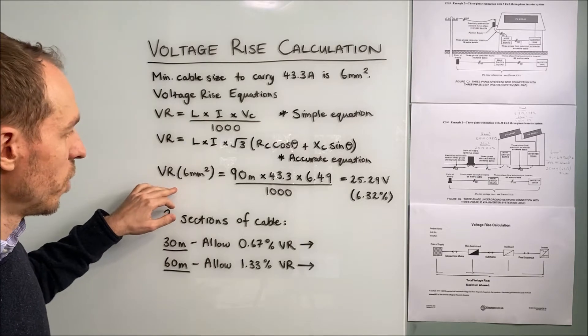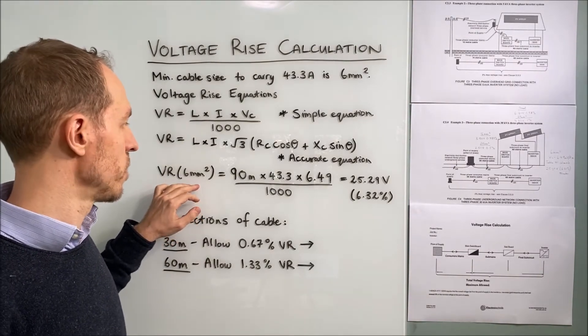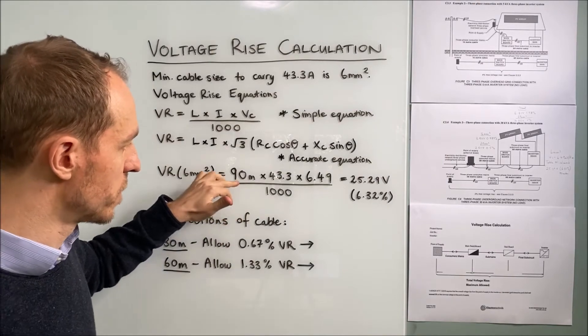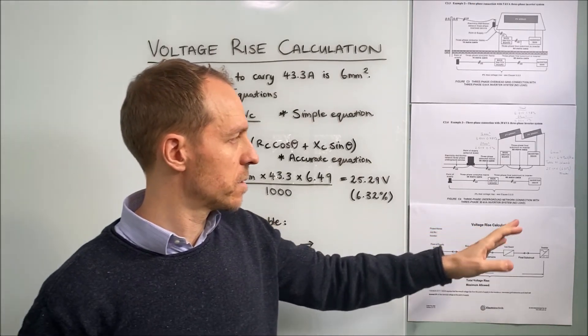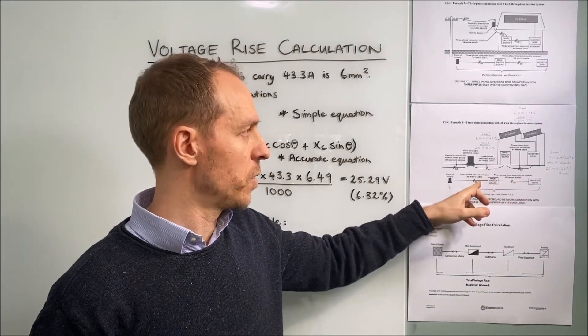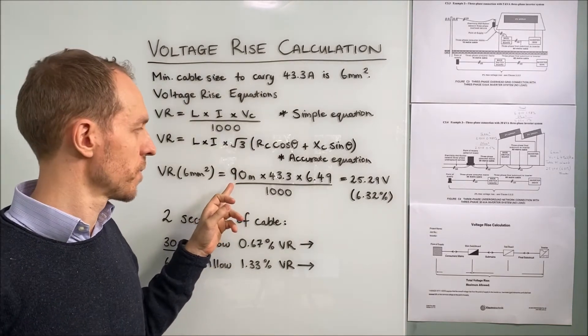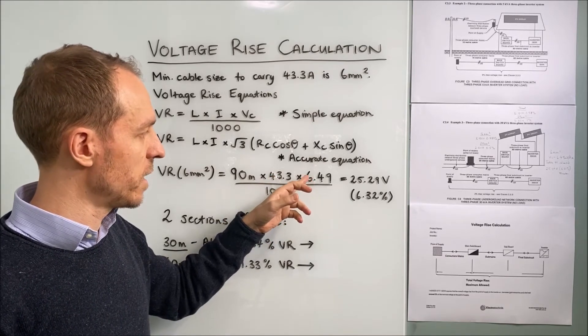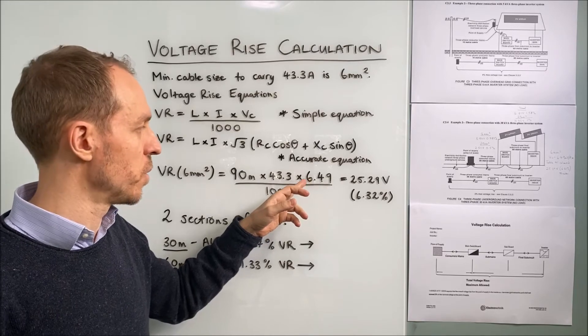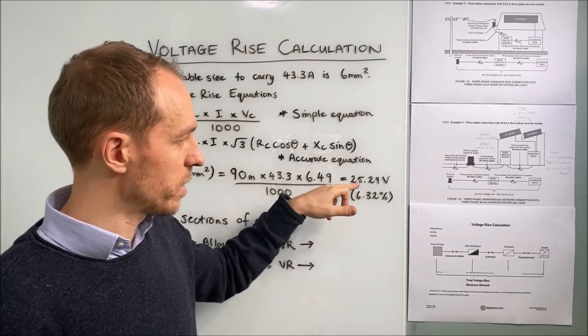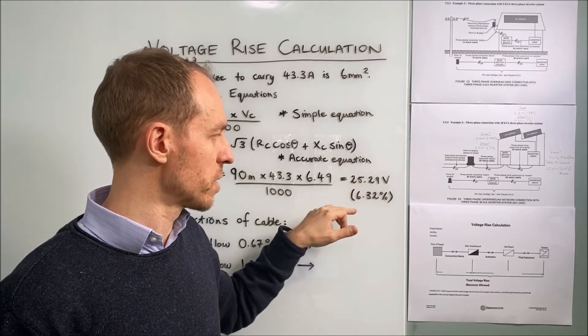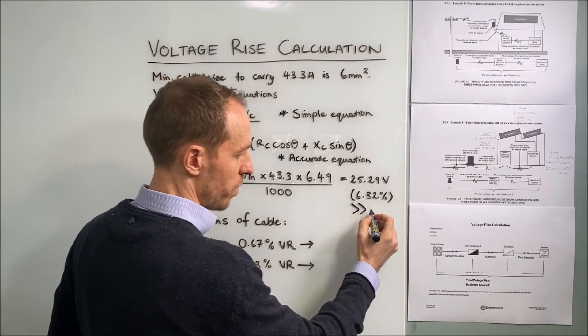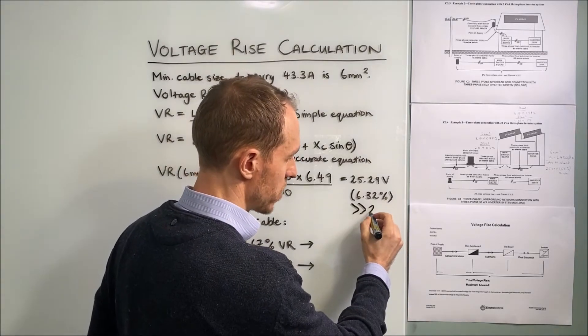So first thing we'll work out the voltage rise for our minimum cable size of 6 square millimeters. We're going to use this simple equation. We've worked it out for the total length of run which is two sections, one 60 meter section and one 30 meter section. Combined that gives us 90 meters. Our inverter output current of 43.3 amps. We've taken our VC value from the standard 6.49 all divided by a thousand. We've worked that out to be 25.29 volts or 6.32 percent which is much greater than our allowable requirement of 2%.